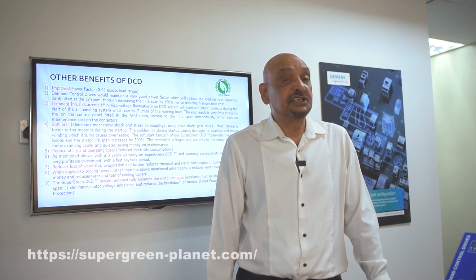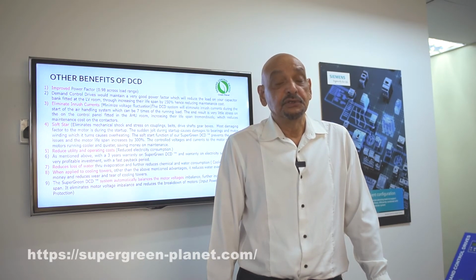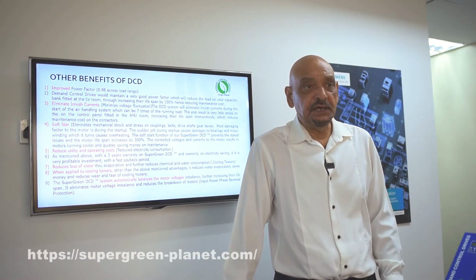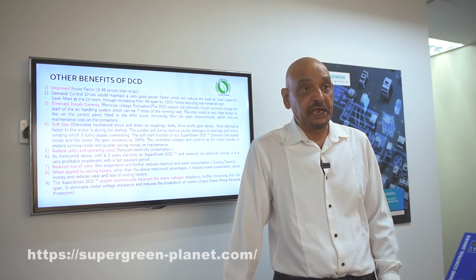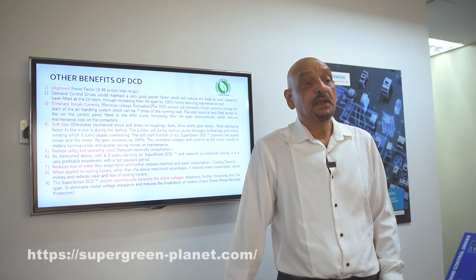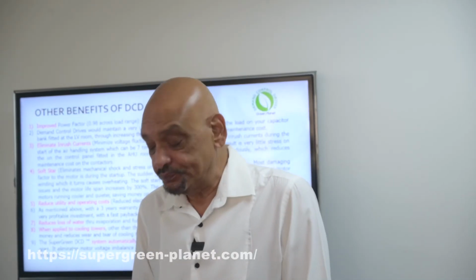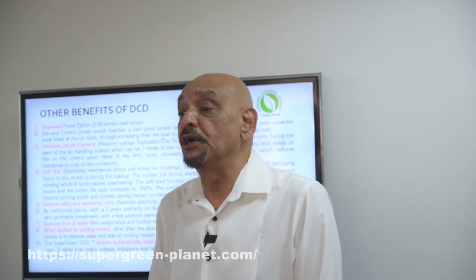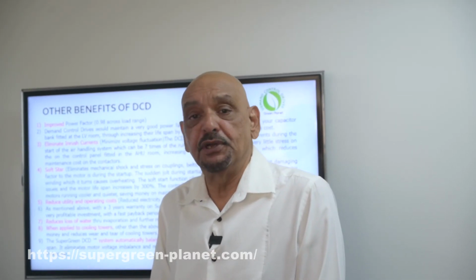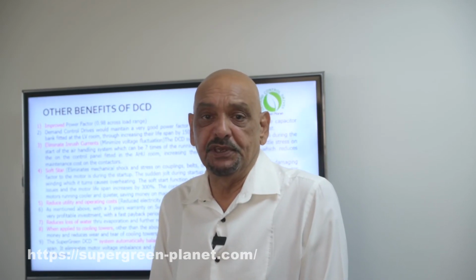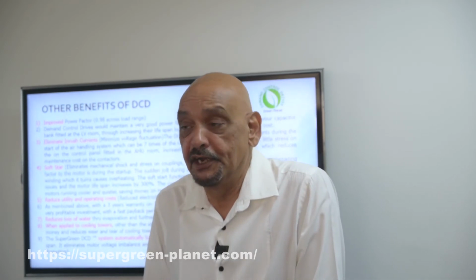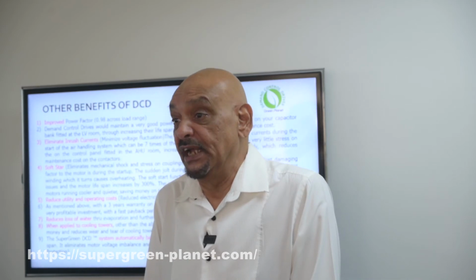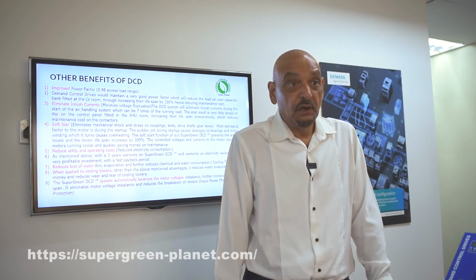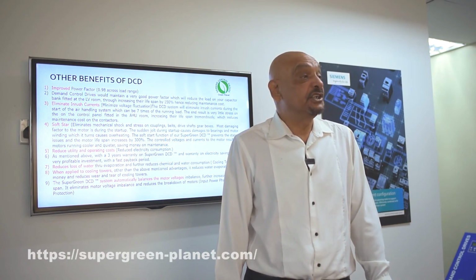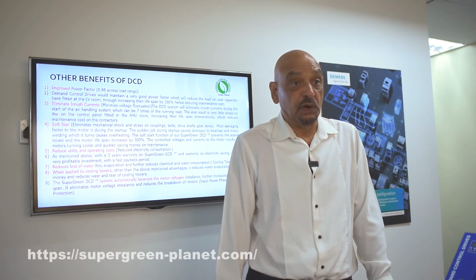If the system detects a fault 3 times within that 1 hour, it indicates that there is a permanent fault. If there is no detection again, it's a temporary fault which the DCD is going to clear by itself. When a permanent fault comes in, the DCD system is going to shut down your equipment and sound an alarm. An alarm can be sounded in many ways. You may have a beeper in your AHU room itself. You may have a beeper outside your AHU room and a strobe light where guards can detect that and report. You may want to send this information up to your BMS, or you may even want to wirelessly send this information out in whatever means you want, which can be done.